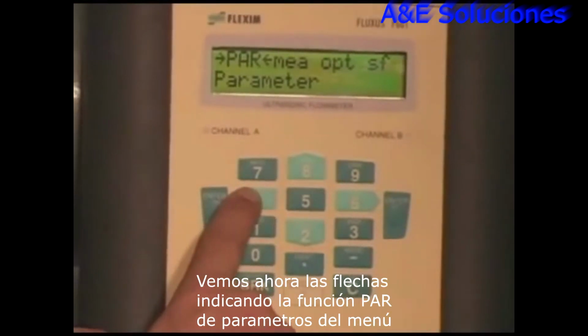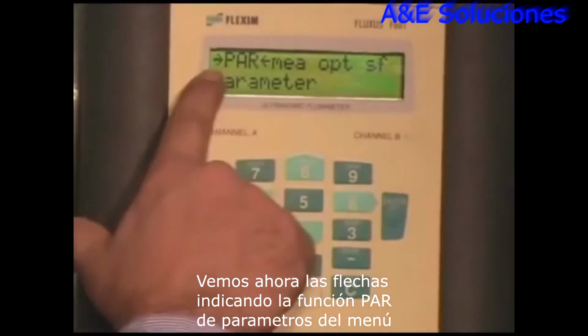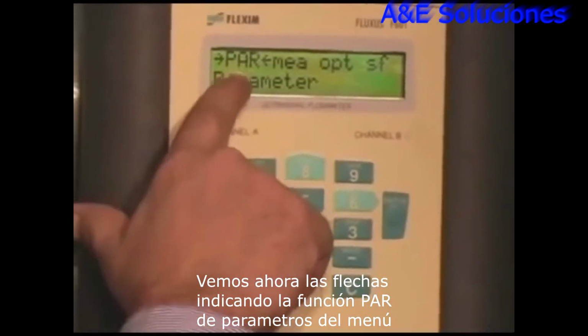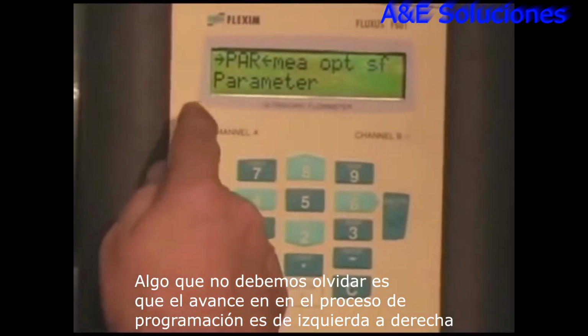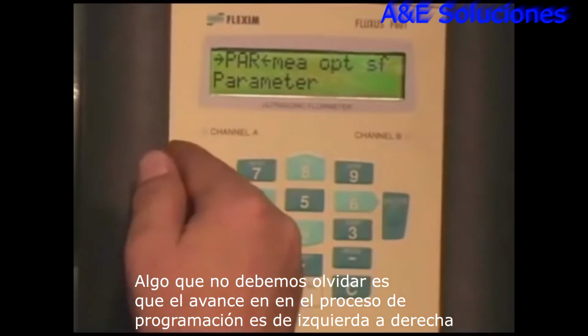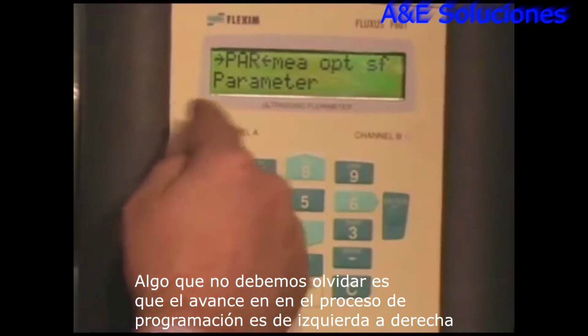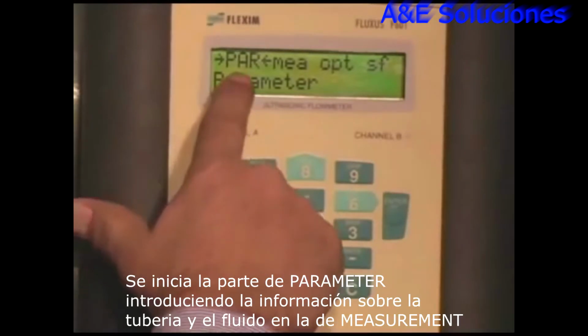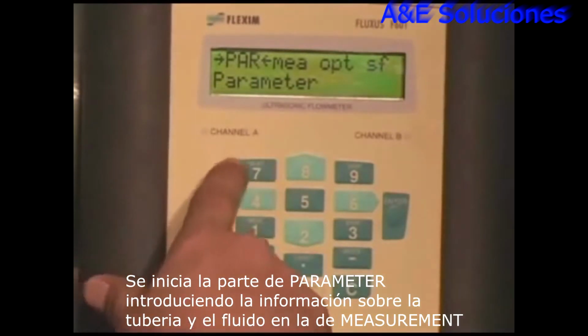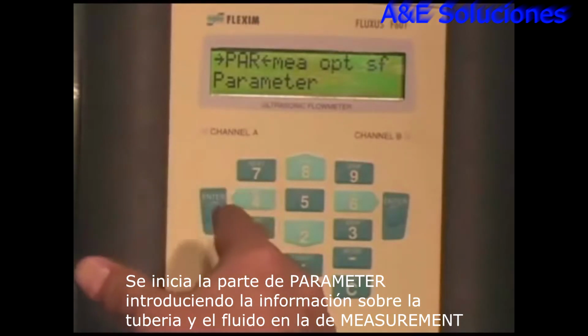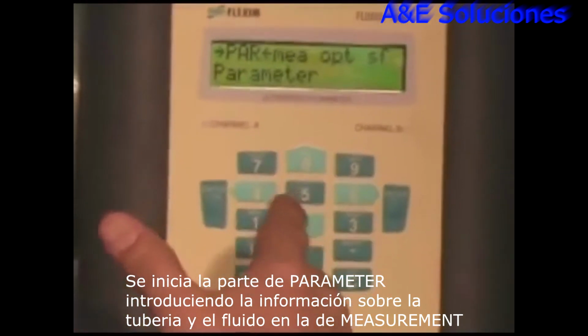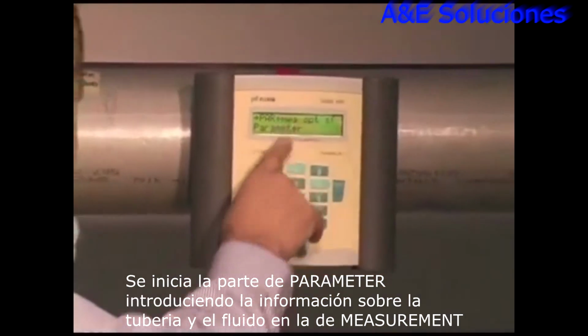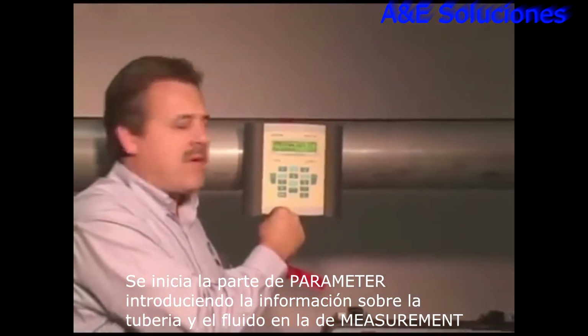Okay, so we pressed our arrow key over, and now we see that the arrows are on the parameters part of the menu. And the thing to remember here, quite simple, is that we're going to do our programming from left to right. So we're going to start at parameters. Parameters is where we're going to enter in the pipe information about the pipe and liquid. And the measure screen is where we're going to go to take our measurement.